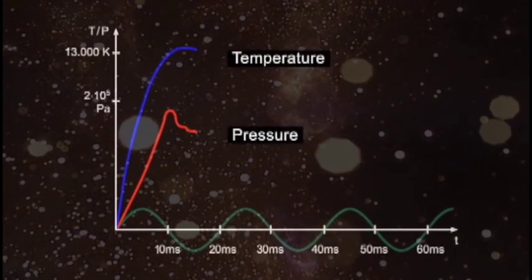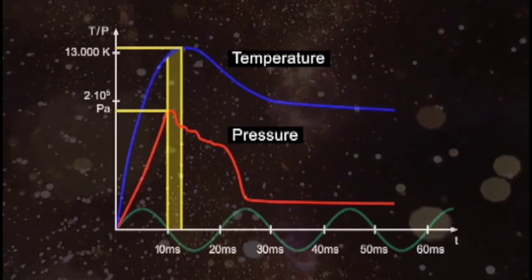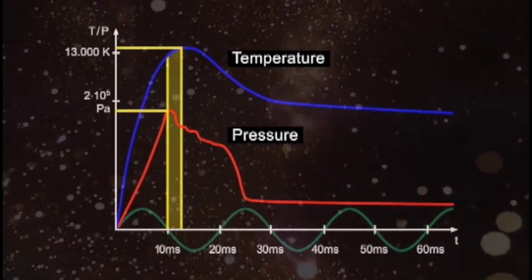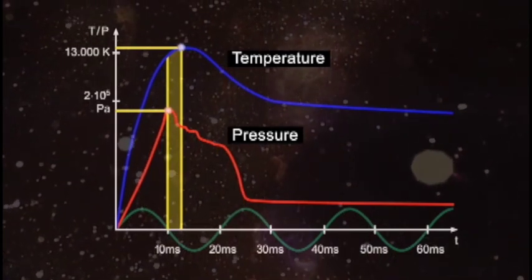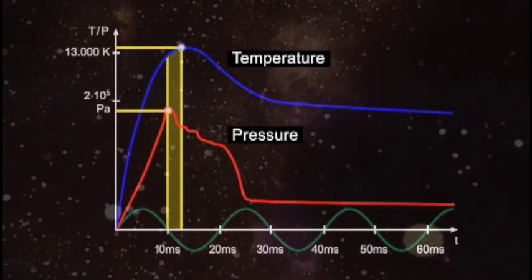In case of a failure, within the first 5 milliseconds, current and magnetic forces reach their maximum. Within 10 milliseconds, the maximum value of pressure follows, while the temperature rises steeply and uncontrollably.